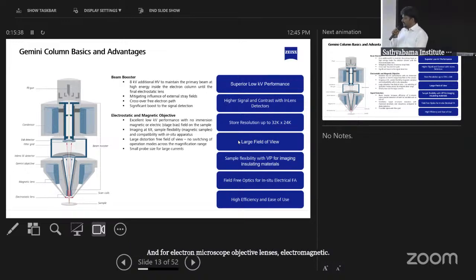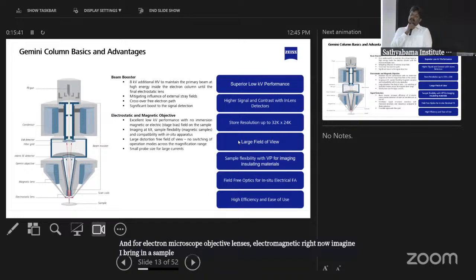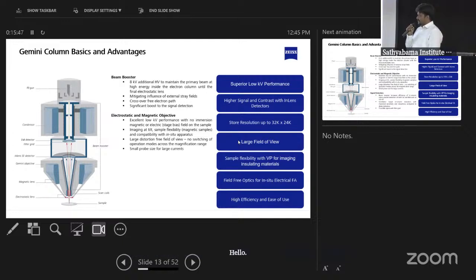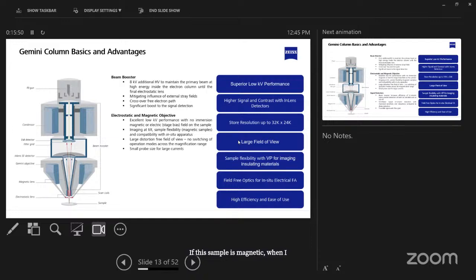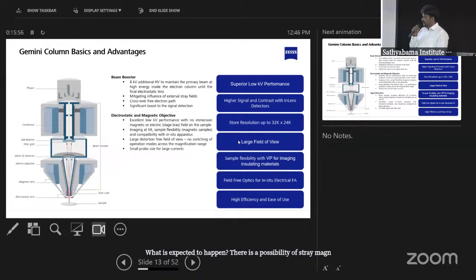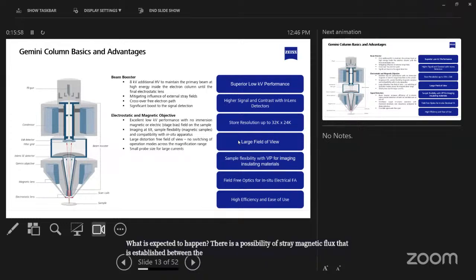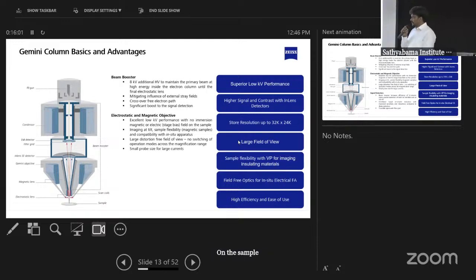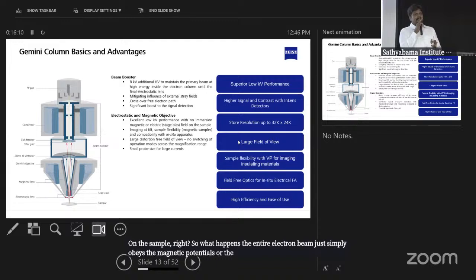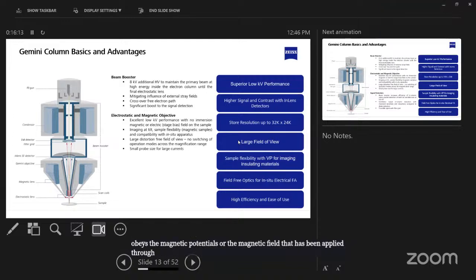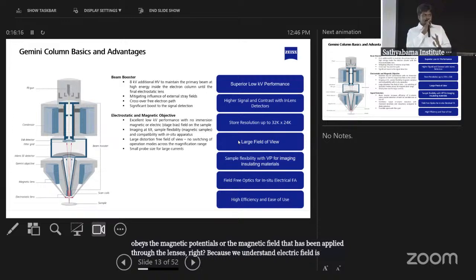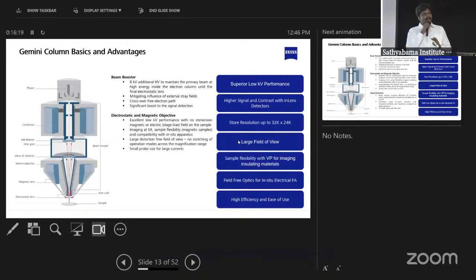Now imagine I bring in a sample which is quite magnetic, or even a rare earth magnetic material. If this sample is magnetic, when I try to bring it close to the objective lens, what is expected to happen? There is a possibility of stray magnetic flux being established between the objective lens and the sample, right? So what happens? The entire electron beam simply obeys the magnetic potentials or the magnetic field applied through the lenses, right? Because we understand the electric field is perpendicular to the magnetic field. Okay, you're all with me?